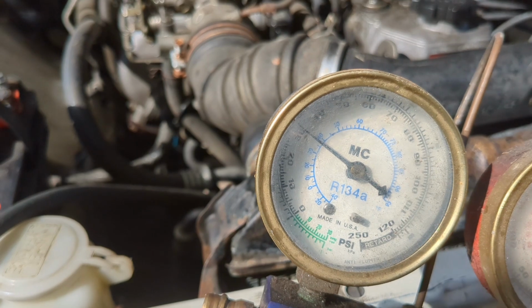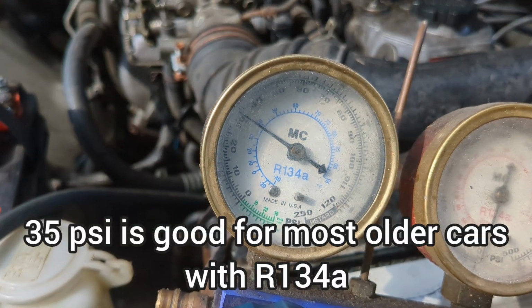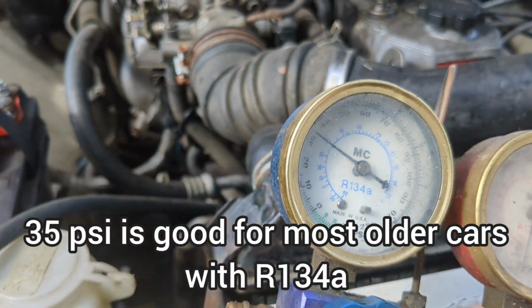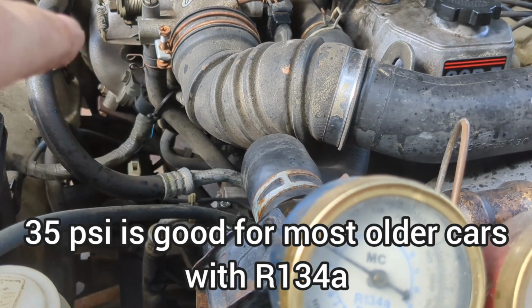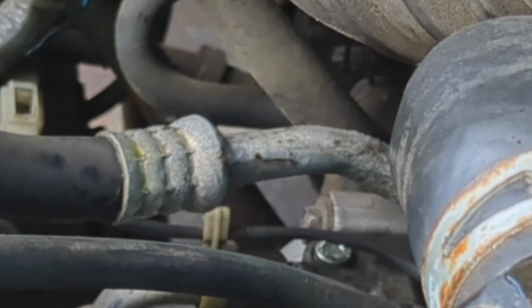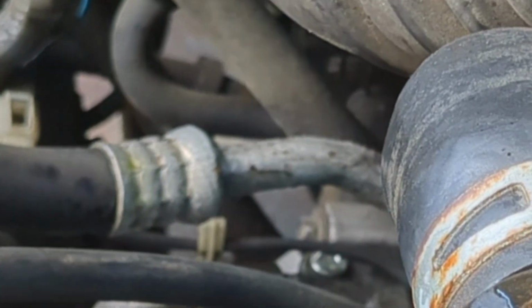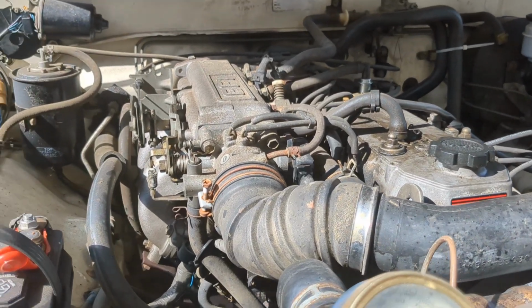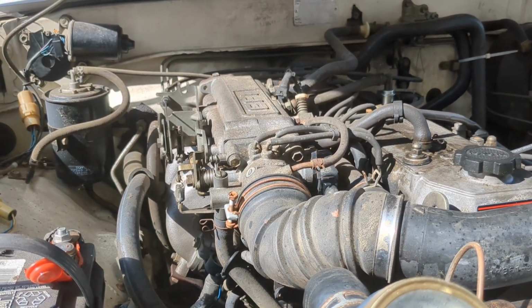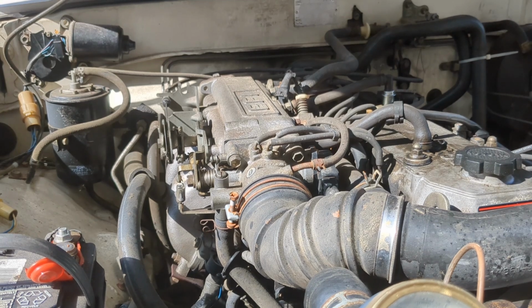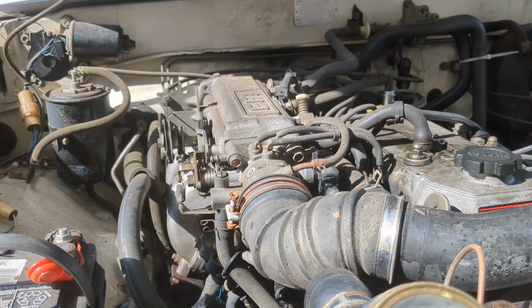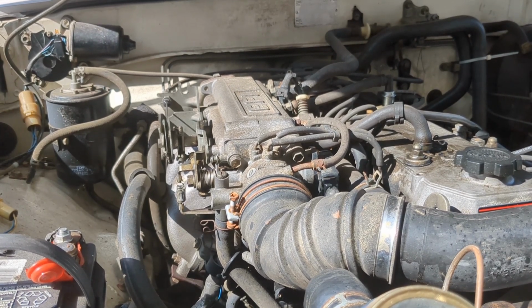We got it down to between 30 and 35 on the low side. You can see that fat line has a lot of condensation on it, overcharged. That could have been from the leaves in the evaporator and the fan, which may have made me inadvertently overcharge it. That happens sometimes.